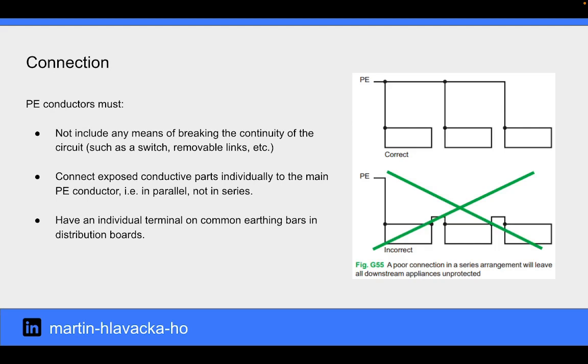PE conductor must not include any means of breaking the continuity of the circuit, must connect exposed conductive parts individually to the main PE conductor, and must have an individual terminal on common earthing bars in distribution panels. The diagram shows how a poor connection in series arrangement will leave all downstream appliances unprotected. The connection should be in parallel.